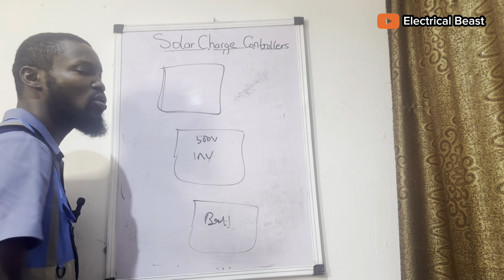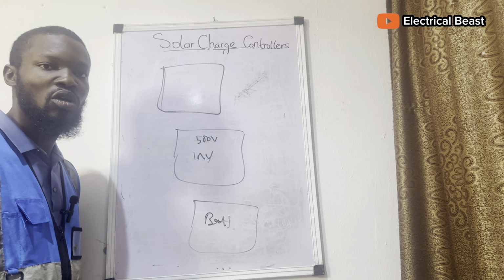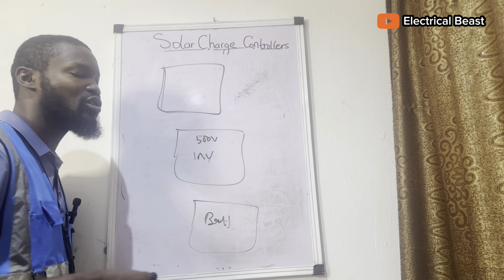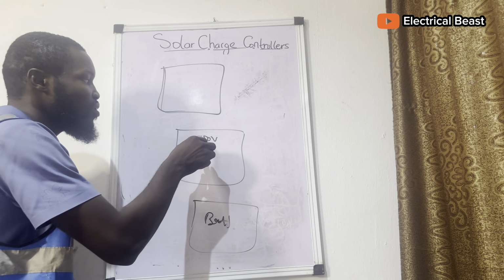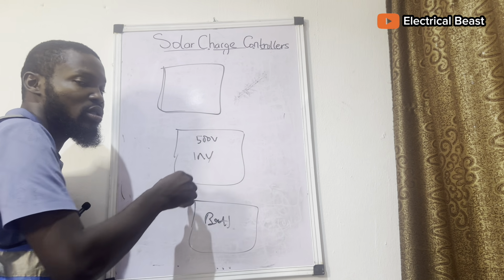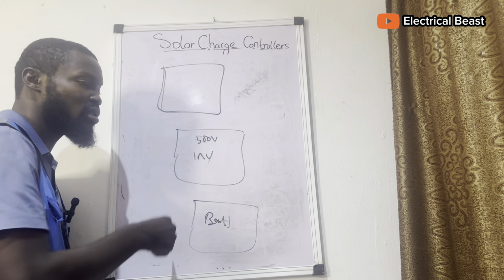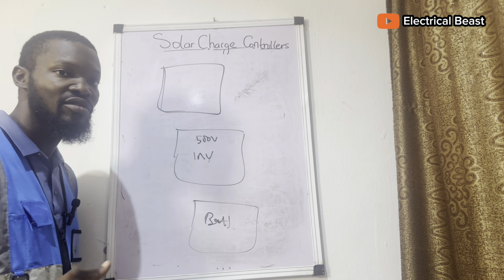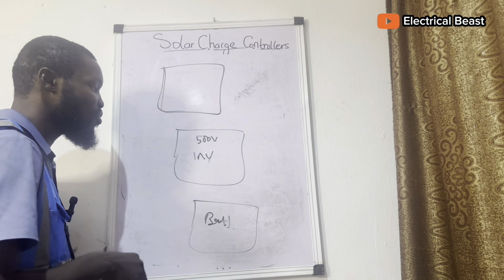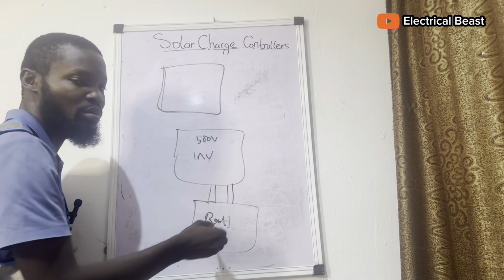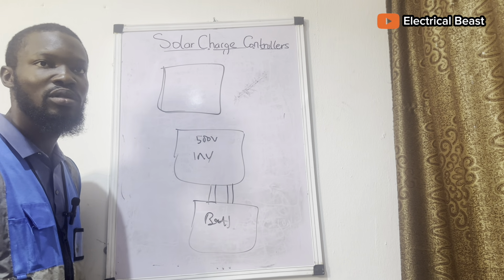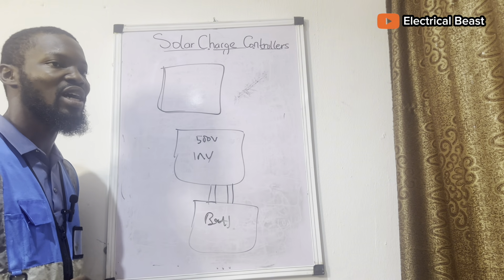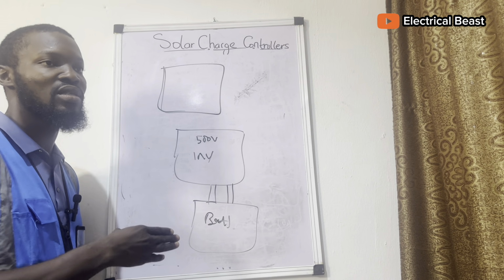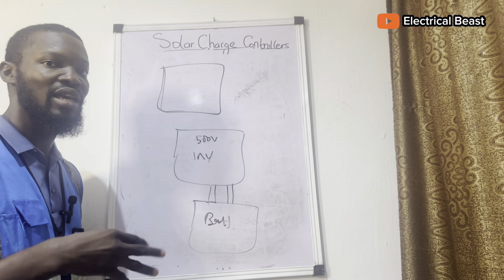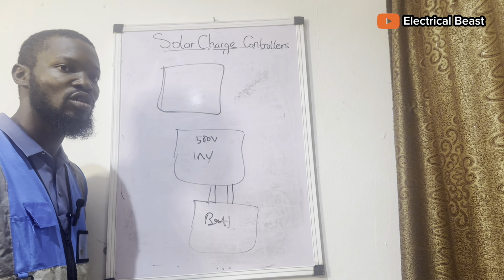For hybrid inverters that have controllers inside, they don't work with a lot of current, they work with voltage, because they are actually high voltage inverters. You can have up to 500 volts. Connect your system within 500 volts for the inverter to work. The inverter needs high voltage and low current to convert and give you the needed current to charge your battery. So you don't need to worry whether you have 10 panels or 9 panels; you want to connect everything in series to give you a small current and high voltage.